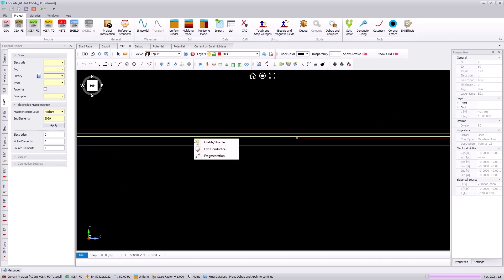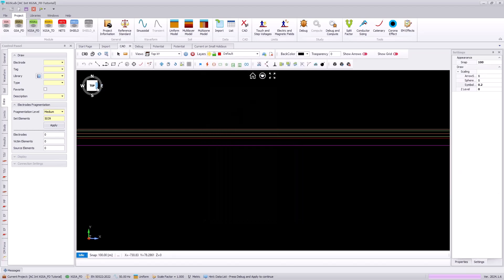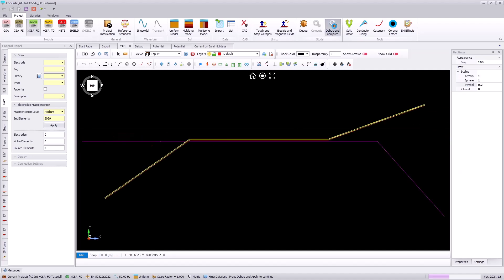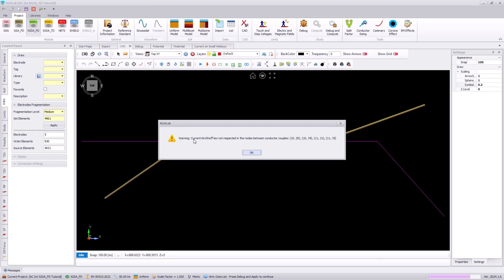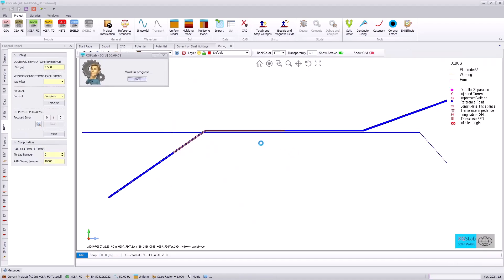Now we can see that if I select one of my phase conductors, the current is dramatically increased, representing a fault condition. We are going to hit debug and compute. Note that the errors shown are indicating that some components will, based on the forced source currents, not be respecting Kirchhoff's current laws — this is an expected warning from our template. The analysis will take longer because the more significant fault current on our phase conductor is inducing a higher voltage on our pipeline, which will exceed the voltage threshold of our surge protective devices.